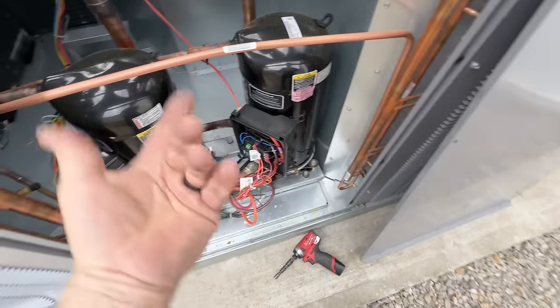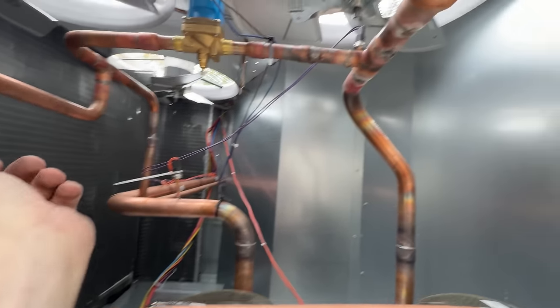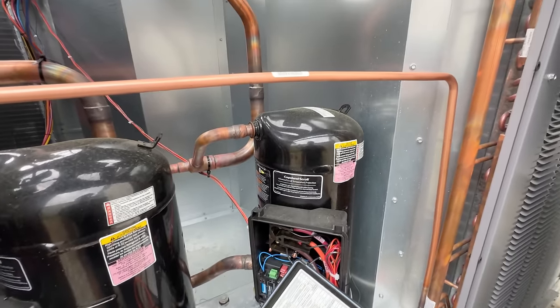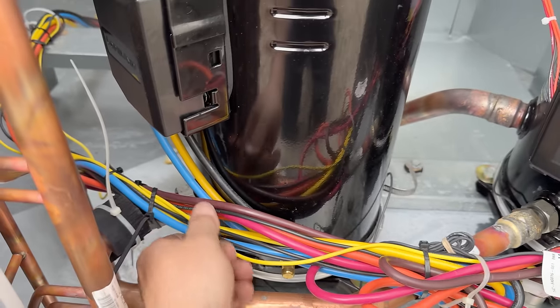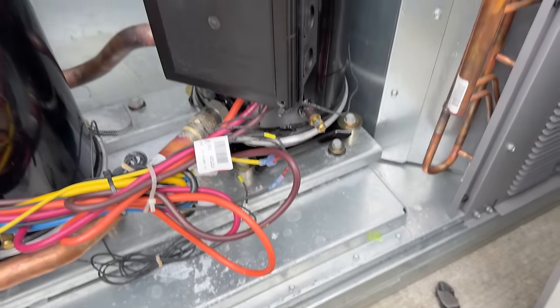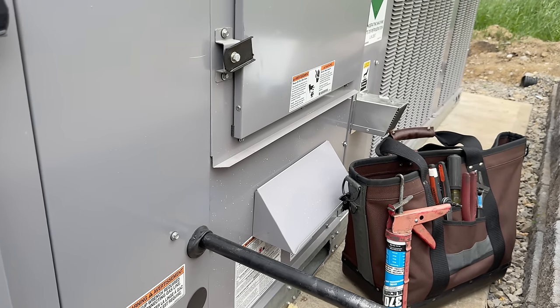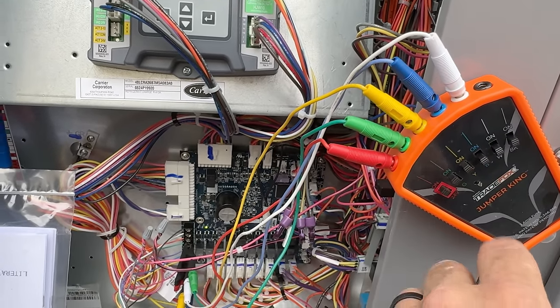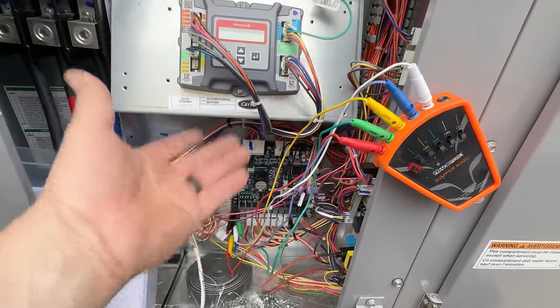So we're finally at the last one. Open it up — that's been exposed for who knows how long. Cover fell off like it did on the other ones. I was able to run a wire tie through there and hold that on. We've got to hurry up and get the gas pressure set and make sure the compressors work — rain is starting to come again. We just got the temperature rise done. Now we're doing the three-stage here. I'm pretty impressed — I didn't think it was going to be worth it. The fittings they've got really do make a difference, and it makes it easy to kick it on and kick it off instead of slipping, dropping, or shorting something out on the board.